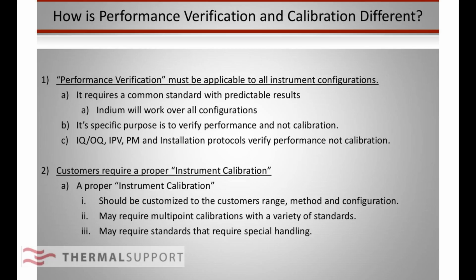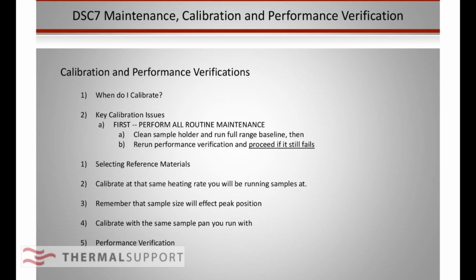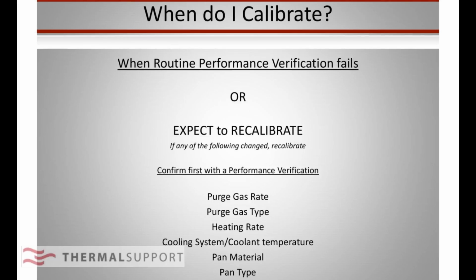So, next slide, calibration and performance verifications. We're going to talk about when do you calibrate, some key calibration issues, selecting reference materials. You want to talk about calibrating at the same heating rate, sample size, sample pan, and doing a performance verification. So when do you calibrate? When routine performance verification fails.